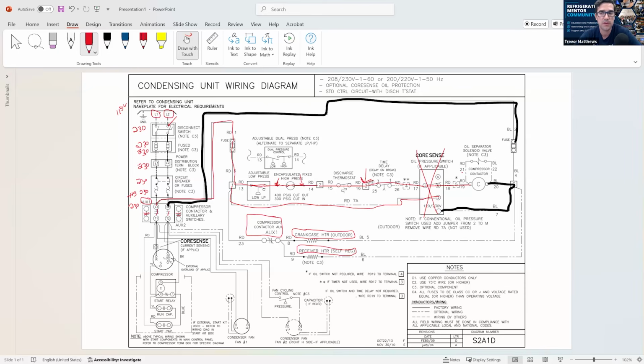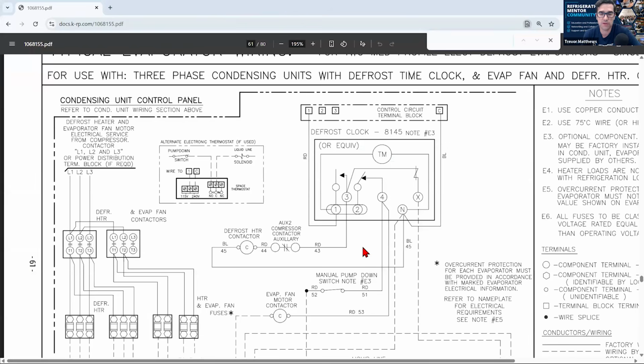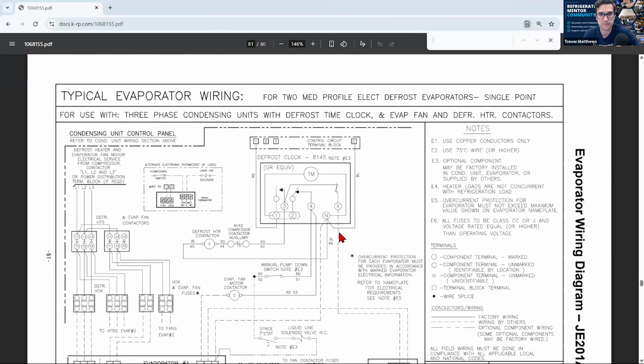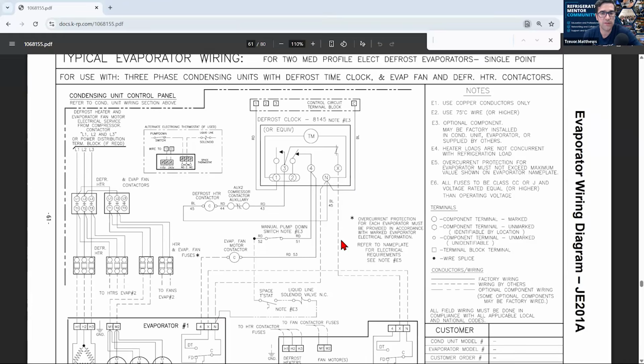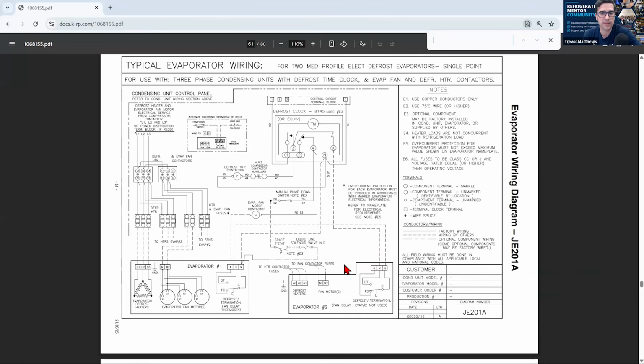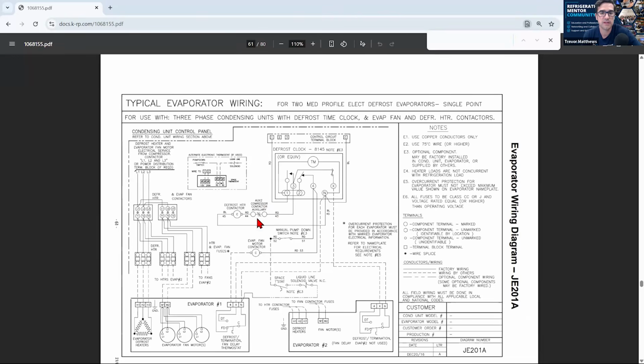This is something important. And then getting into the manual, for those that are watching this, I'll pull the manual over, because I just pulled this right out of one of the Keeprite manuals. And then here's the evaporator side. Okay, I couldn't find auxiliary 2 on that last one, but auxiliary 2 is right here. Auxiliary 2 will close when the compressor is off, because it's normally closed, and that will energize the defrost heater contactors. You're doing electric defrost. And that doesn't come on unless the defrost time clock is enabled or has made in this one here.